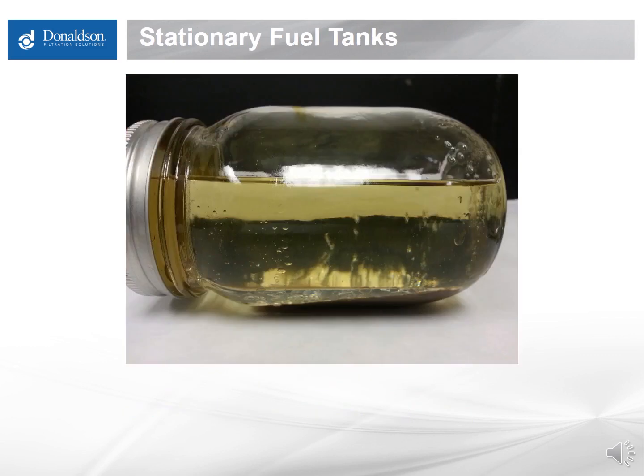Moving to what people more normally consider fuel issues: dirt and water in storage tanks. In a stationary fuel tank, gravity does a pretty good job of settling dirt and water to the bottom over time. However, water is a contributor to solids formation — both with glycerin and other additive reactions. You should not let water build up; prevent it using routine tank cleaning, desiccant breathers, or purging the reservoir headspace with dry air to prevent condensation. We have webinars on this topic on MyCleanDiesel.